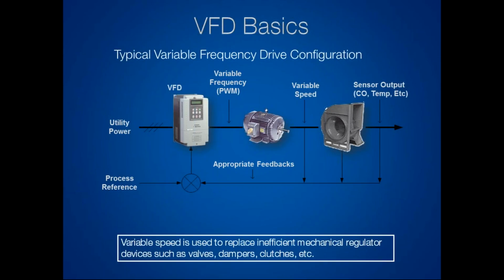So we've got our line power coming in. Let's say we've got 460 volts coming in. We've got that line power coming in, it's going into your VFD, then it's actually talking to your motor. It's telling your motor what to do, okay? Maybe your motor is speeding up, slowing down. There's going to be some sort of process output that's telling our VFD to speed up or slow down.